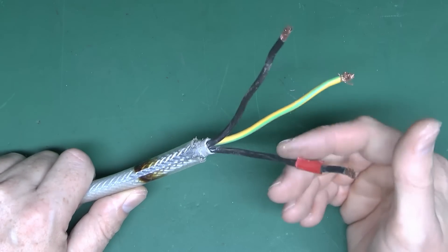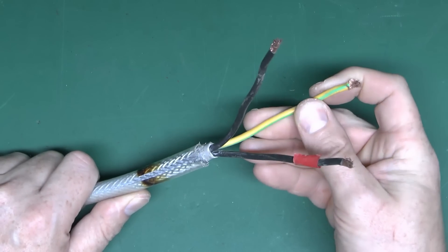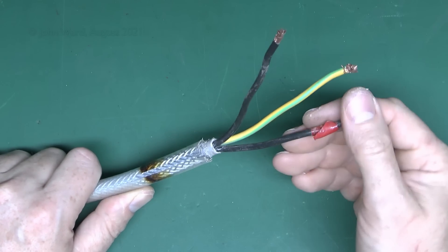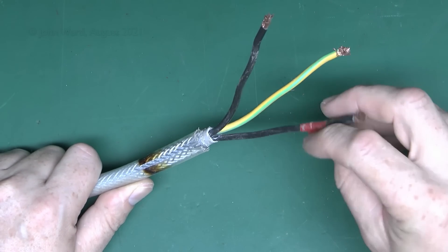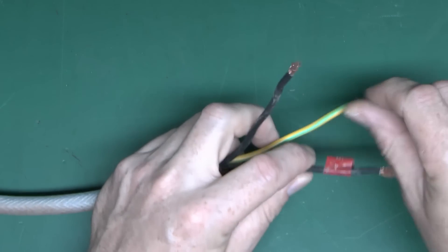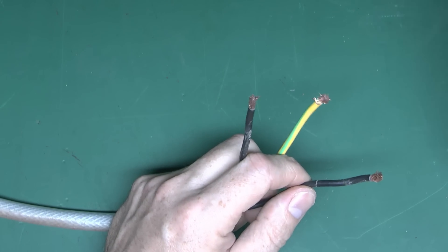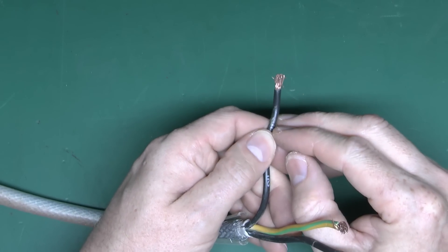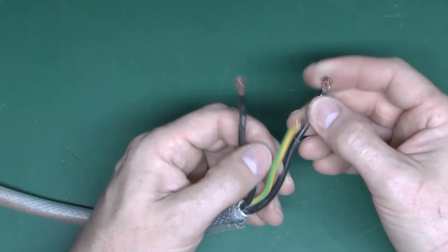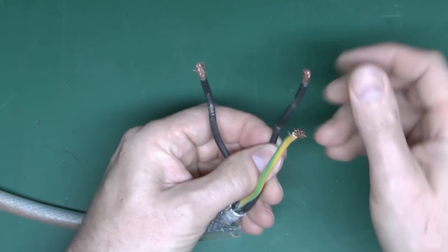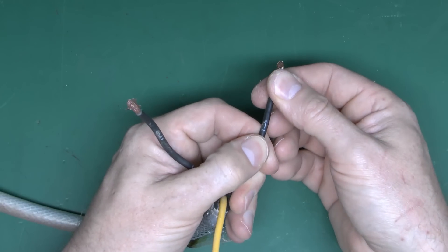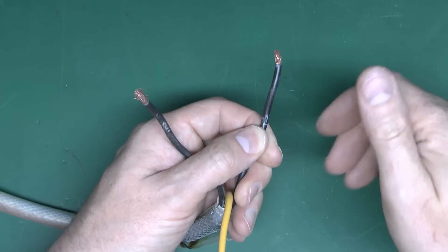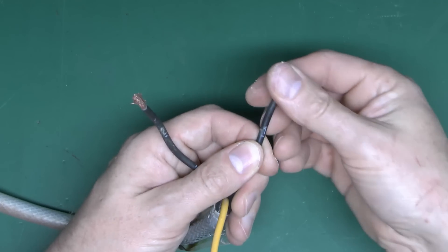Now this happens to be a 3 core cable, or 2 core plus the protective conductor. Protective conductor green and yellow as you'd expect. The other two are black. This one has got a bit of red tape here where someone has identified the line or live. The proper identification is actually these numbers. You can see on this one just about number 2 printed there, and this one should have a number 1 on it. Notice that they're underlined, so then you can check which way up they are.